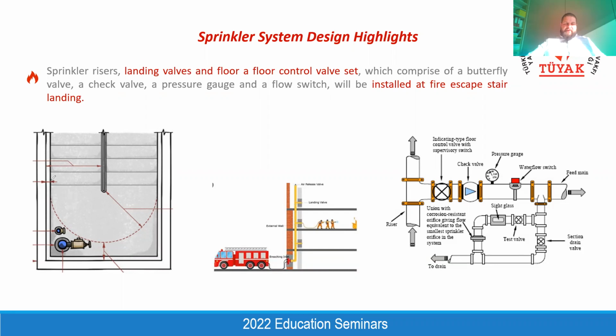But the location is also important. According to the clear width of your staircase, there will be a stair circle here. You need to draw it on your plans, and all of the equipment, both the riser, the landing valve, and if you have a drainage pipeline, should be located at the outer areas from this staircase semicircle. Because these areas should be used by the people who are escaping from fire, and these dead areas can be used for the sprinkler system equipment to be located. It means on the red areas we are not allowed to locate sprinkler system equipment, but within these other areas we can locate our riser, our landing valve, and also the gate valve group.